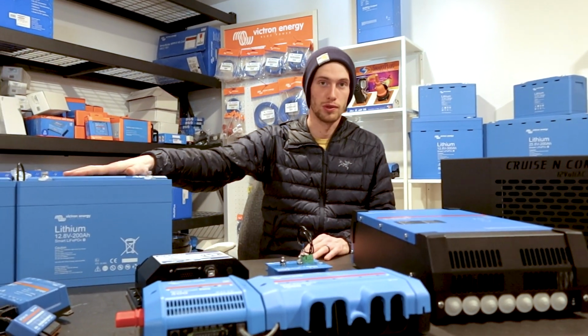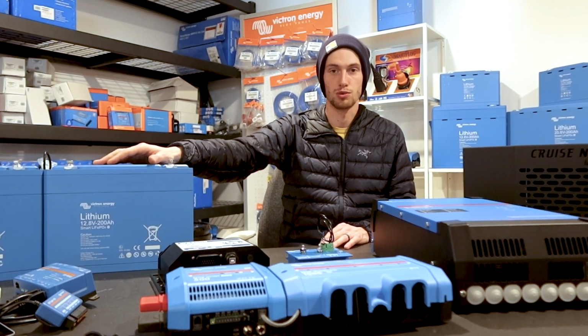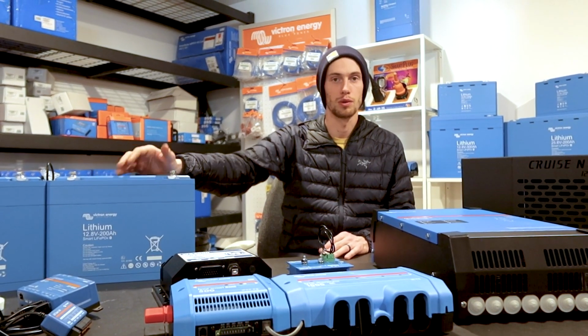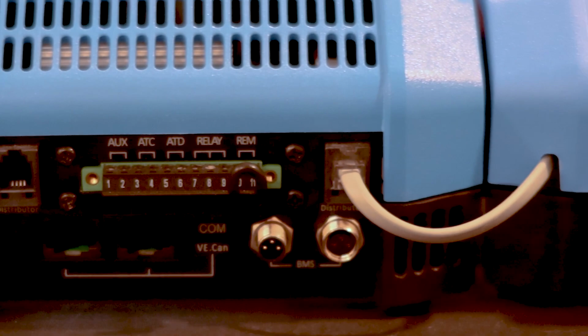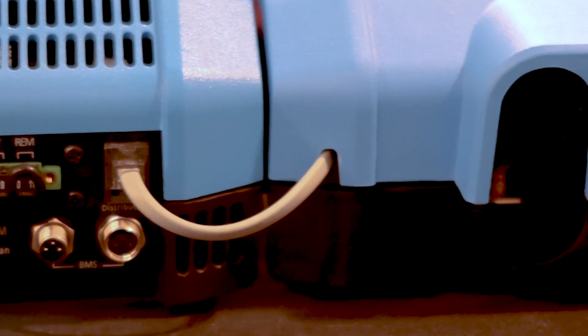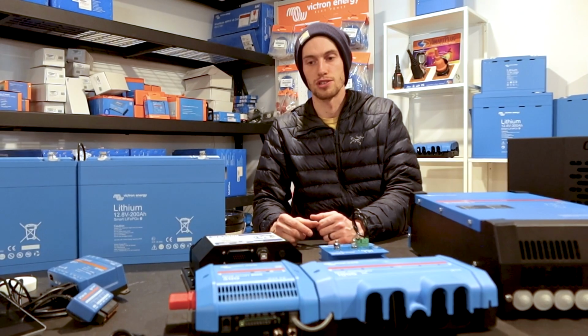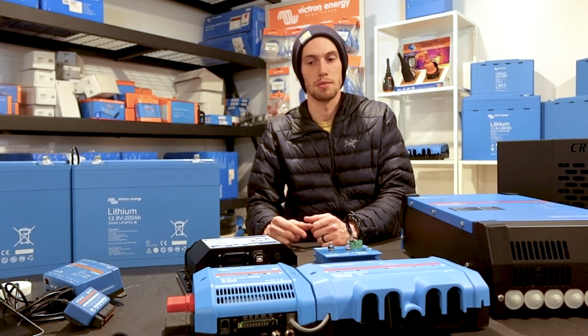Normally, if this was a 12 or 24 volt system using 12 or 24 volt batteries in parallel, we would combine them on a bus bar and then into the LYNX BMS, or into a LYNX In and then the BMS. With this, because we're only going to have a single negative and positive coming off, we're just going to go directly onto the LYNX Smart BMS.